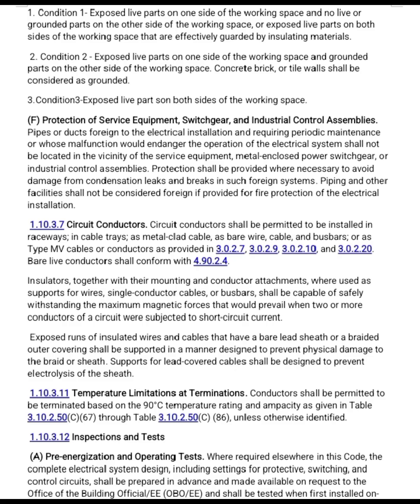Pipes or ducts that are not part of the electrical system should not be placed near switchgear or control equipment, especially if they need maintenance or could leak. Leaks can cause damage or electrical faults. If pipes are installed only to protect the electrical equipment, they are allowed.